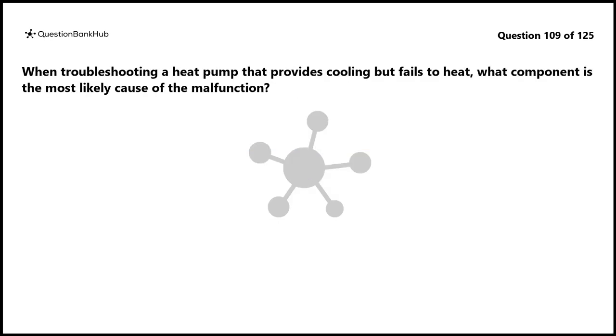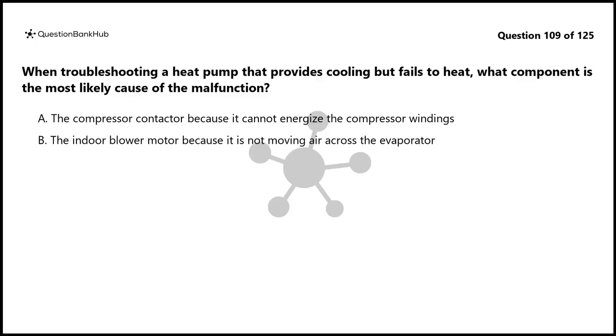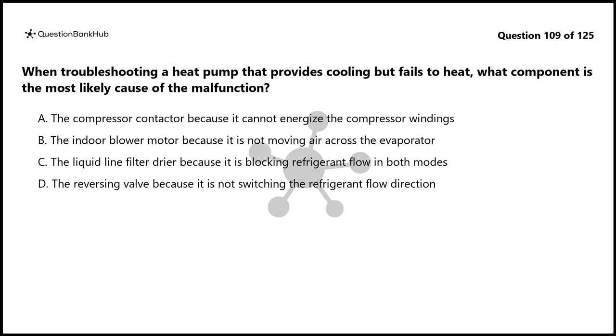Question 109. When troubleshooting a heat pump that provides cooling but fails to heat, what component is the most likely cause of the malfunction? A. The compressor contactor because it cannot energize the compressor windings. B. The indoor blower motor because it is not moving air across the evaporator. C. The liquid line filter dryer because it is blocking refrigerant flow in both modes. D. The reversing valve because it is not switching the refrigerant flow direction.